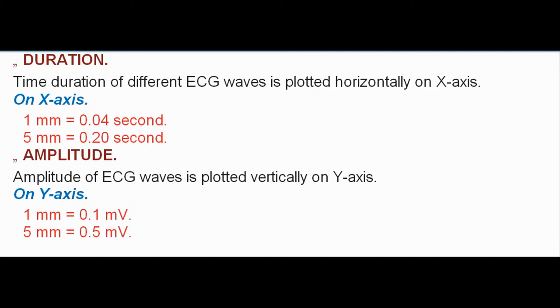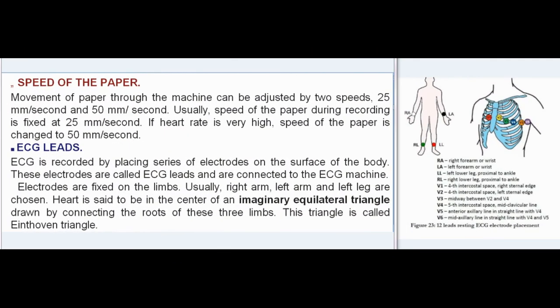On the y-axis, 1 mm equals 0.1 mV and 5 mm equals 0.5 mV. Speed of the Paper: Movement of paper through the machine can be adjusted at two speeds — 25 mm/second and 50 mm/second. Usually, the speed of the paper during recording is fixed at 25 mm/second. If heart rate is very high, speed of the paper is changed to 50 mm/second.